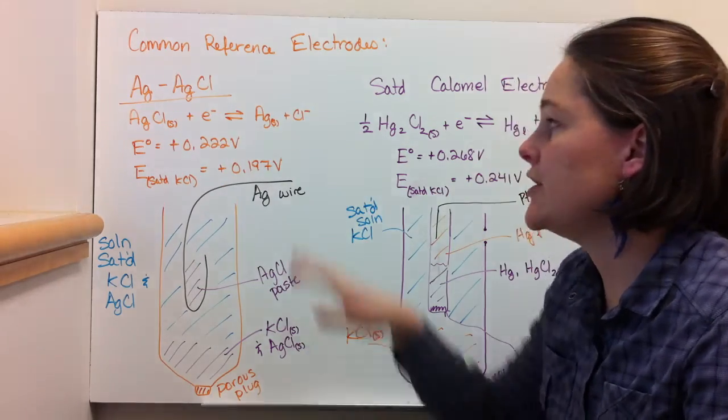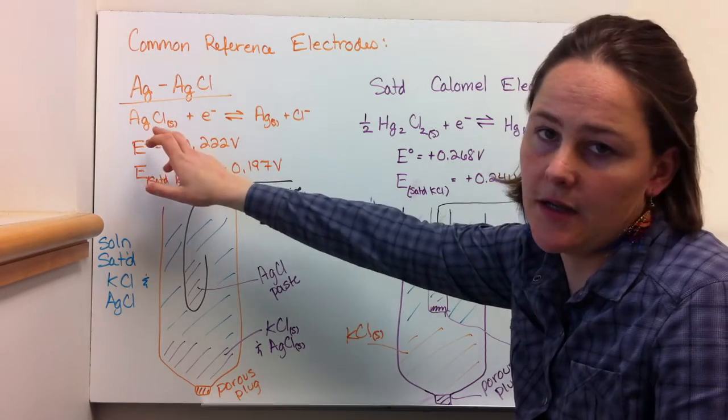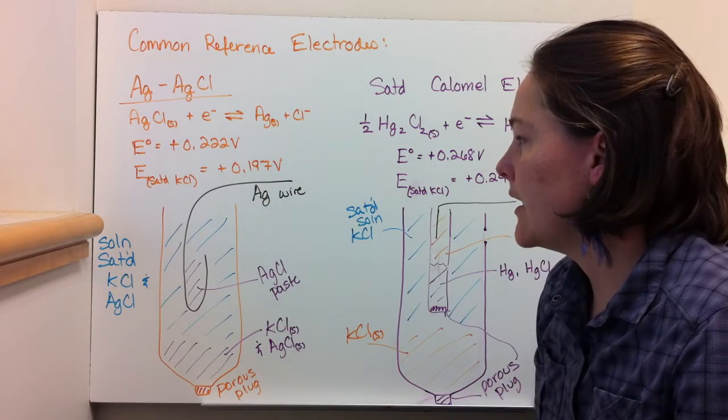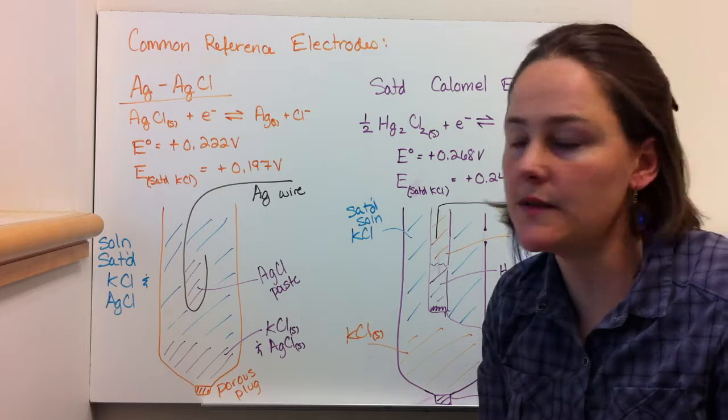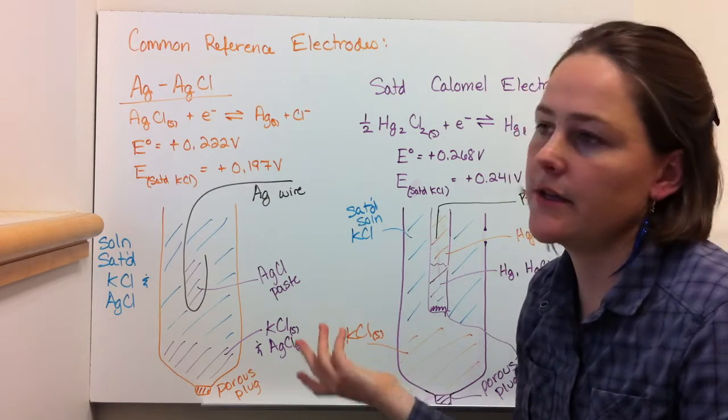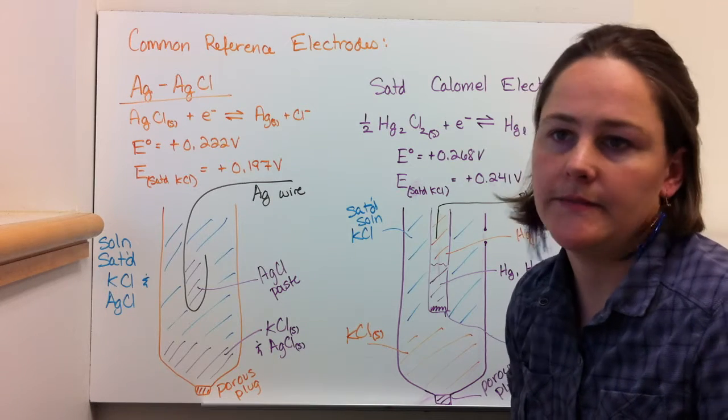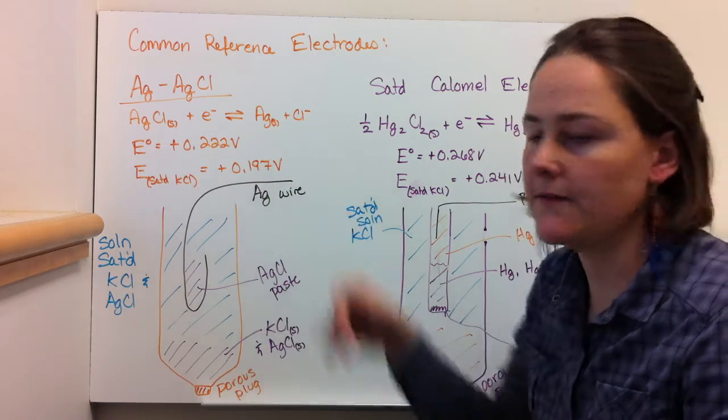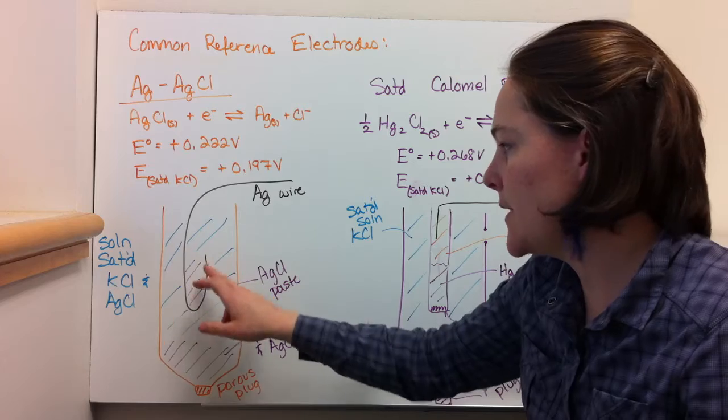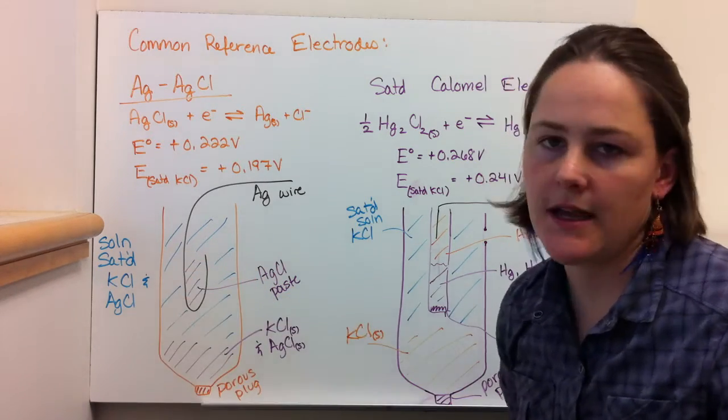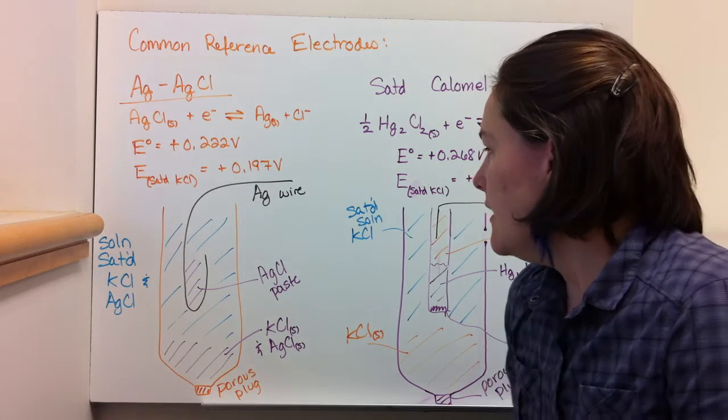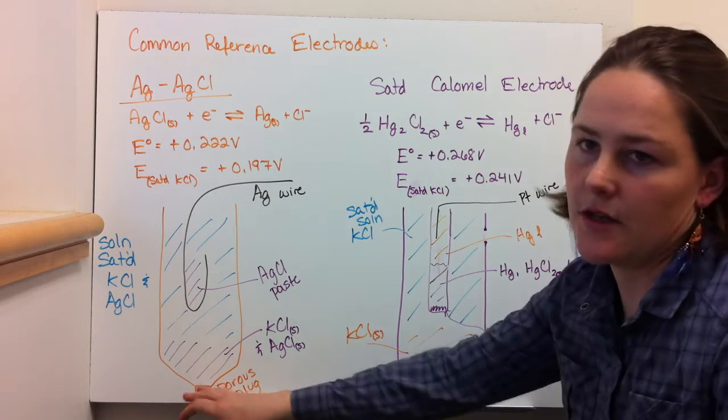Here is an AgAgCl electrode where you have AgCl solid taking an electron in to form silver metal plus chloride. The E0 is 0.222 volts. But if you calculate it for a saturated KCl solution, which is the conditions that you're most likely to have inside of a reference electrode, then you actually have a different potential. Basically how it works is you have a silver wire coming in with some AgCl paste hanging out in a loop, in the loop of the silver wire. And that's in contact with the solution that's saturated with KCl and AgCl. And then you have a porous plug going to your solution, like a salt bridge.